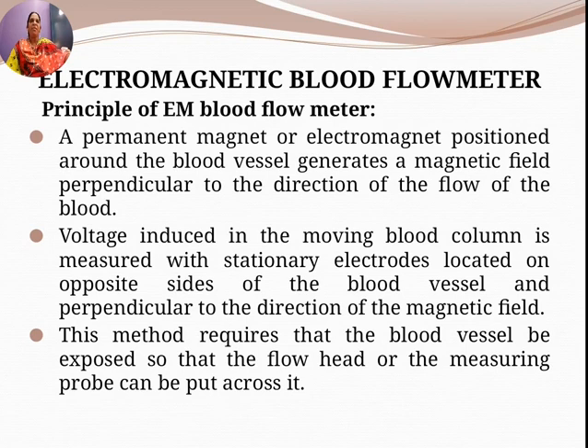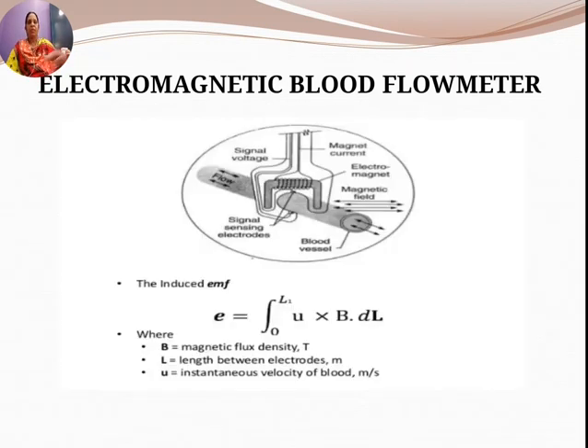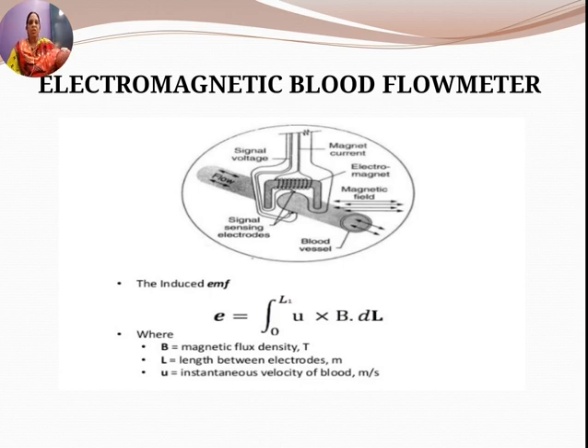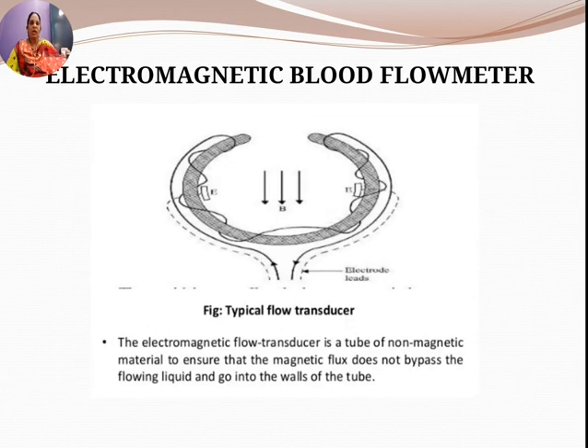The amount of EMF generated depends upon the flow rate of the blood. The induced EMF is proportional to B (magnetic flux density in Tesla), L (the length between the electrodes), and U (the instantaneous velocity of the blood): EMF ∝ U × B × L. So an EMF is induced which is proportional to the velocity of the blood.